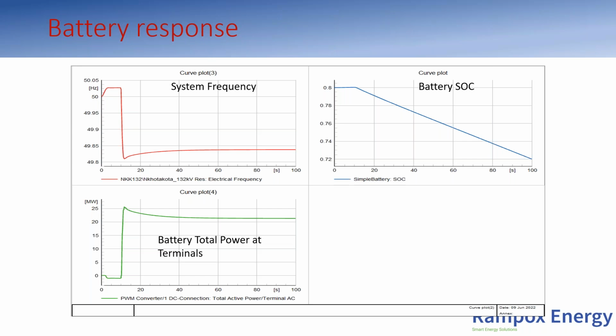That means it will leave a particular margin that the system operator will have determined, saying this particular unit should operate at not more than 90% of its full output, so that room is reserved for primary frequency response, so that when there's an event, that machine can move. Otherwise if it's operating fully, it won't move, so it needs to operate below. The aggregated governing response from all the machines is what provides the reserve margin required to close the gap and arrest the frequency at the required level. But through our studies, we've seen that with the governor, if we keep those amounts of reserves on the governors themselves, even if we increase the level we have now as we put in more renewables...